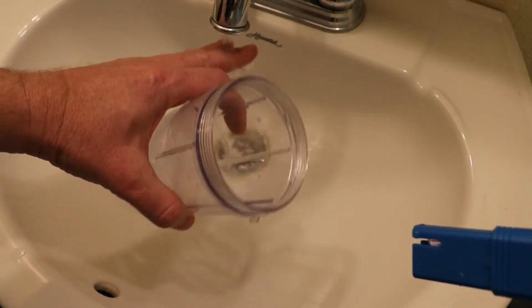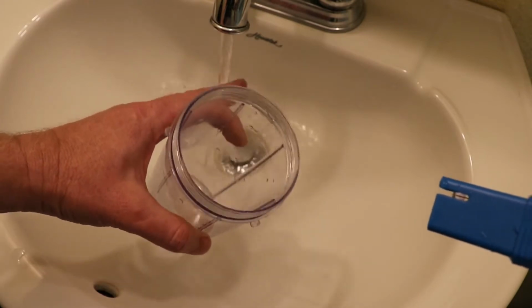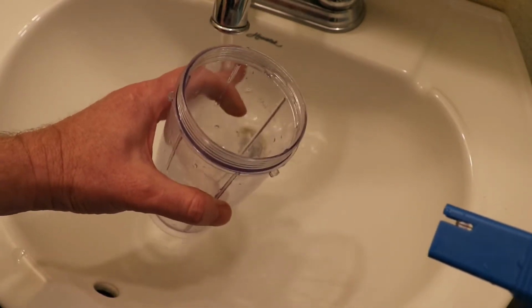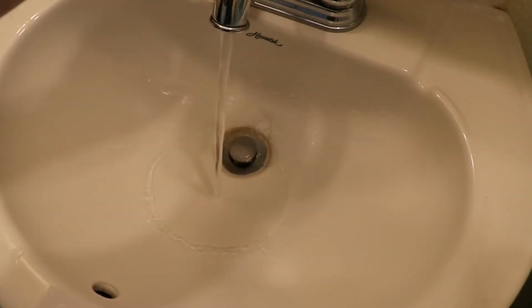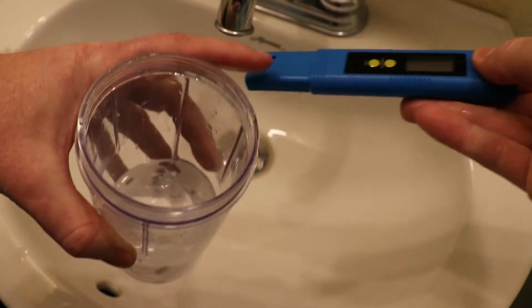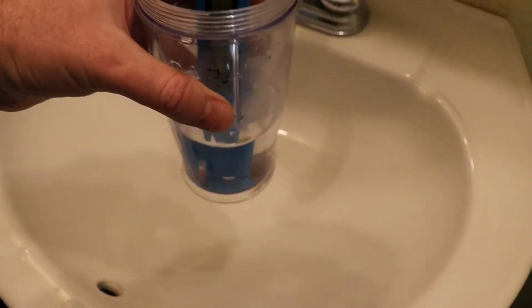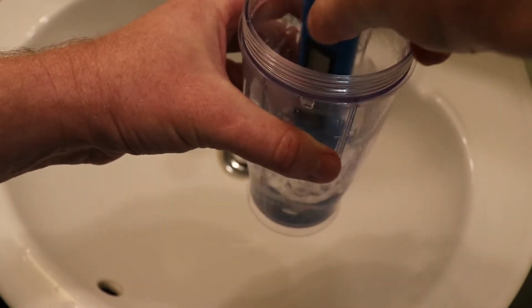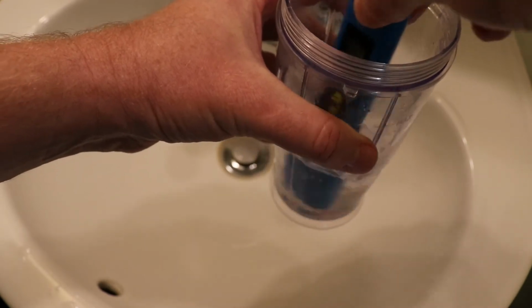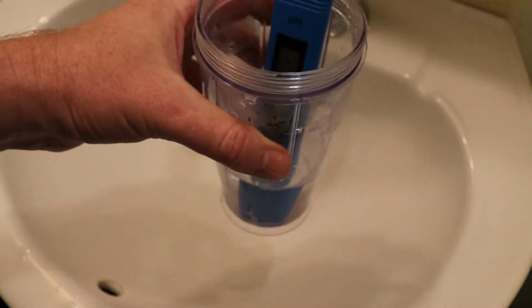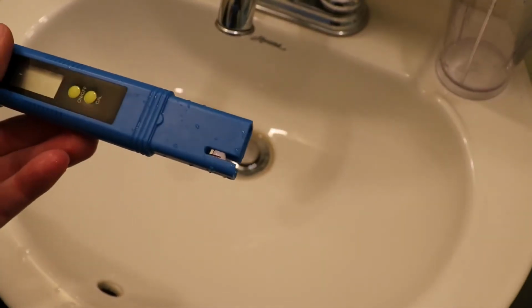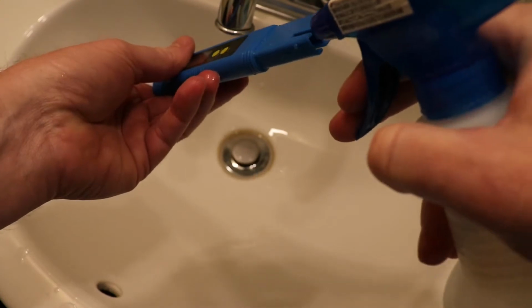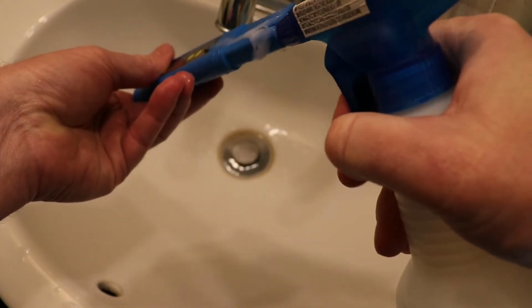Get as hot of water as you have in your water heater. It doesn't need to be boiling or anything, but you know, over 100 degrees. Fill up a container to the point that it's at this level about right here. Stir it around for a while, dislodge any salts or grease grime that's on here. Let this sit for a good 30 minutes. And then after you let this soak for a good 30 minutes, spray it with some IPA, isopropyl alcohol again.